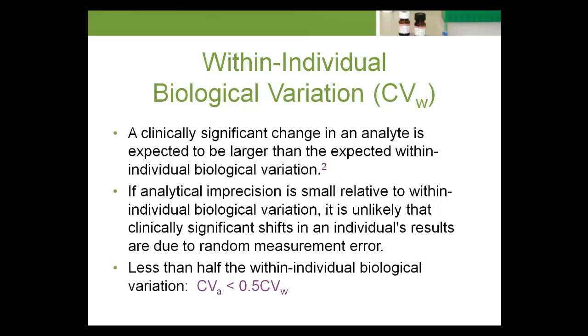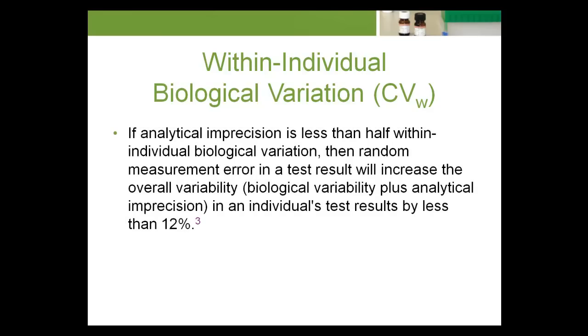A general rule of thumb is that analytical imprecision should be less than half the within-individual biological variation, CVA less than 0.5 CVW. If analytical imprecision is less than half within-individual biological variation, then random measurement error in a test result will increase the overall variability (biological variability plus analytical imprecision) in an individual's test results by less than 12%.